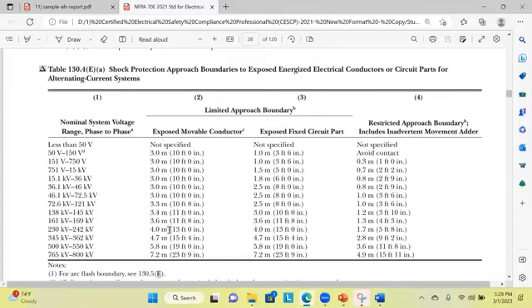In column number 2, for example, an exam question may say that a person needs to work on the 33 kV voltage level. What is its limited approach boundary and restricted approach boundary, and it is an overhead line. We come to this row, 36 kV, where 33 kV falls under this range. We look into column number 2, and the limited approach boundary is 10 feet and the restricted approach boundary will be 2 feet. If it is a fixed conductor, then we will be using 6 feet, not the movable conductor.